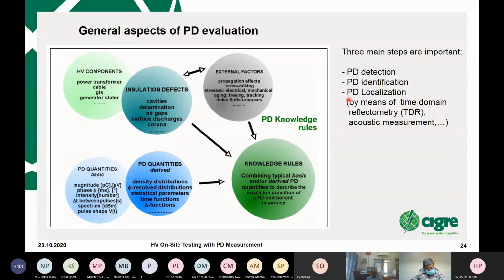But even if you have this and you have the PD signal, the pattern, you can see how complicated the PD evaluation is. For example, different components produce different PD signals and have different PD generation, like cavities or air gaps or corona, like in a GIS or a substation, or surface discharges. And then the different objects, like, as I said, the cable.